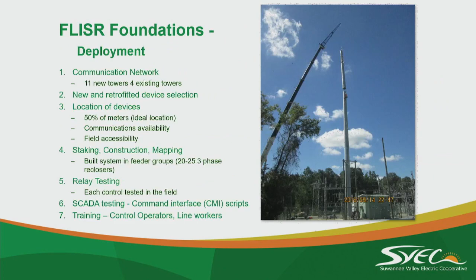Plan terminated, recloser failure. For the restoration of expected load, though, say you had a three-phase device with, for whatever reason, another mechanical failure, and only two of the phases closed in, so that third phase didn't pick up the load. FLISR won't really look at that, but our relay in the field, you can program them. We actually decided to go with triple single. So we're doing three-phase, single-phase tripping and also single-phase lockout. It will indicate, we sent the trip, we expected all three, only two opened. We get an alarm and it may drive the other phase to lockout.